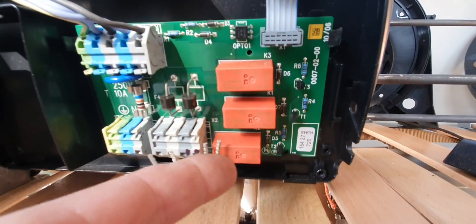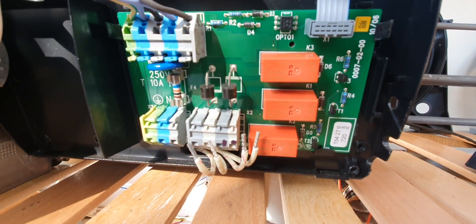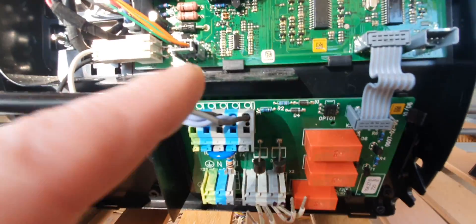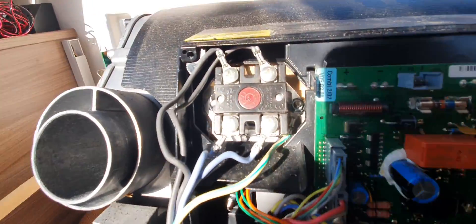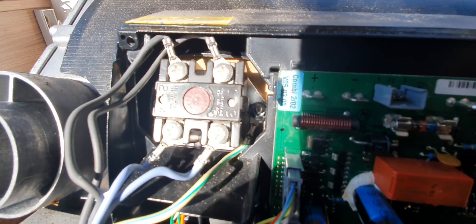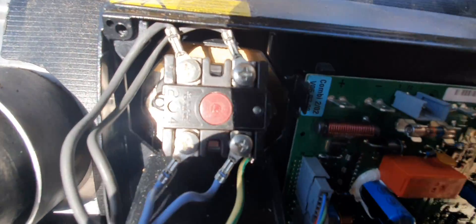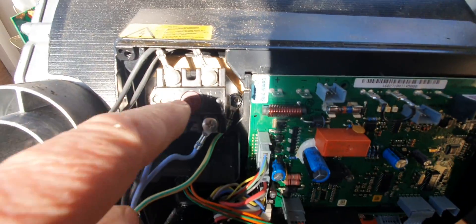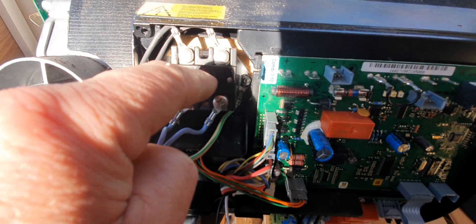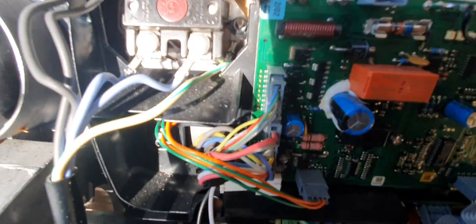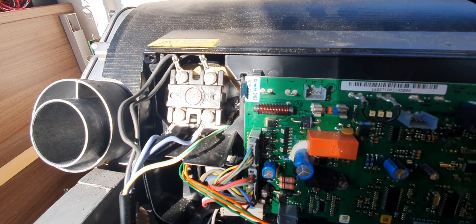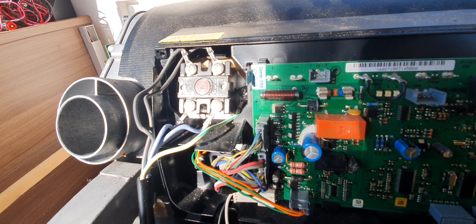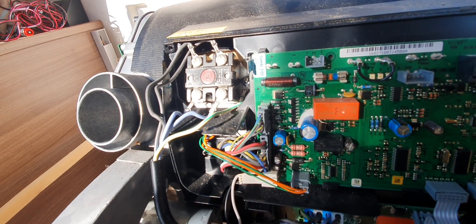Obviously they'll run through these various relays and onto the circuit board. These cables here run up to the thermostat, and that's like a trip override switch which does have a reset button on it in the middle. So should you have any troubles, just make sure that that hasn't tripped for any reason. But of course, I would probably suggest if it has tripped then there's a bigger problem going on.